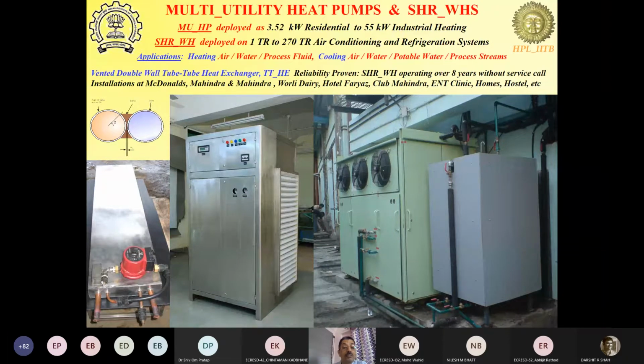Okay, so this judicious integration of this configuration into various technologies that we have developed helps us directly interact with the process fluids in the plant, whether it is a dairy or a chemical factory or an industrial environment like automotive industries and things like that. We can directly heat and cool the fluids. So that eliminates internal extra loops of the heat transfer media and extra pumps and controls for those, and helps improve the COP of the overall installation, because the lift of the heat pump can now be reduced. We don't have to heat up water and then use that water to heat up the process fluid. We can directly heat the process fluid. So one LMTD is eliminated, and so our heat pump COP also improves.